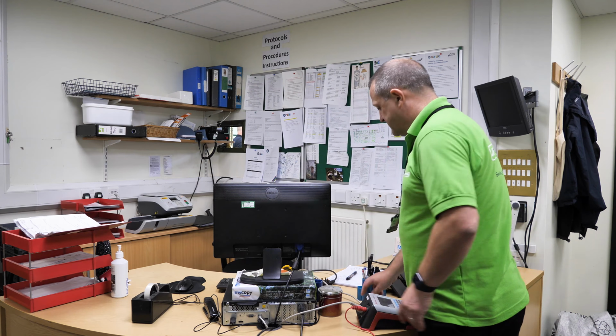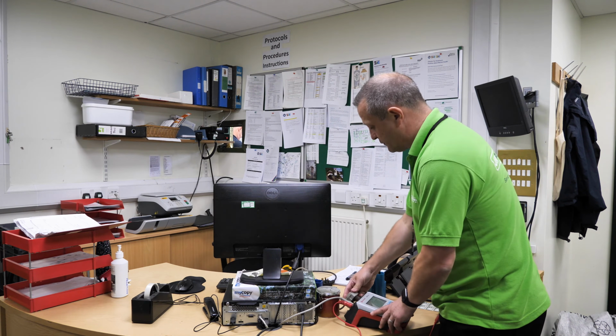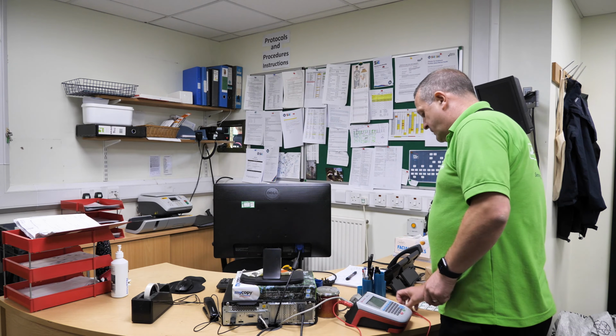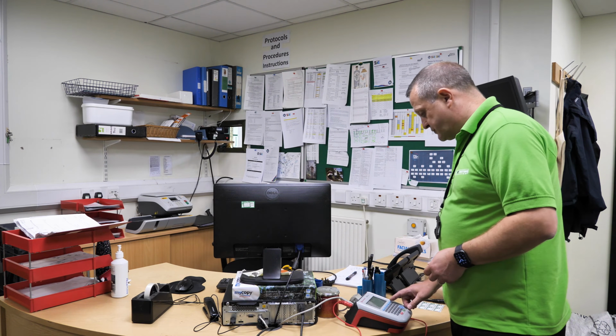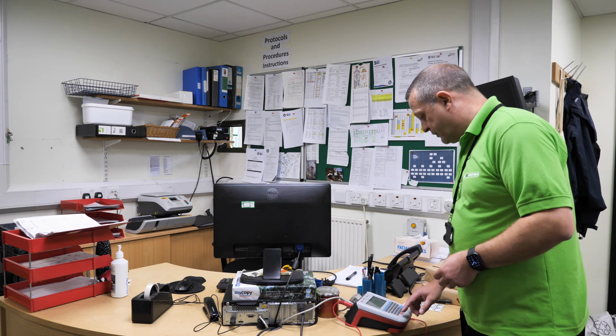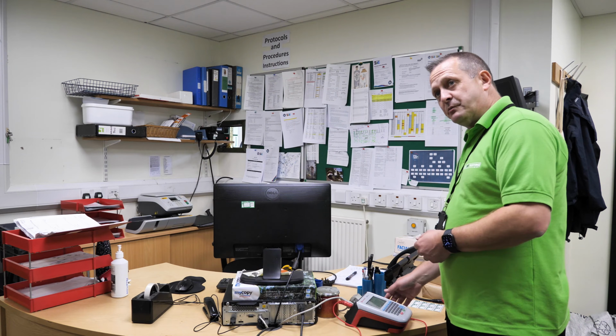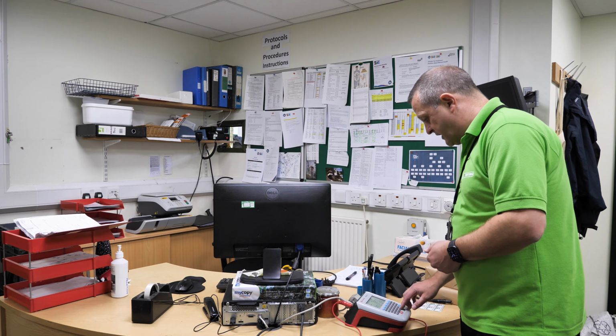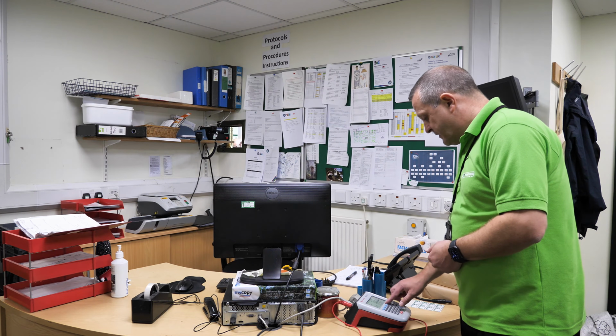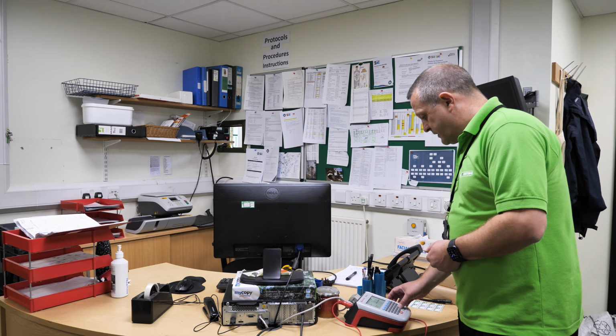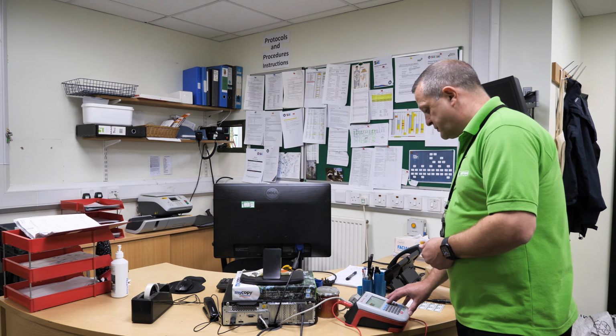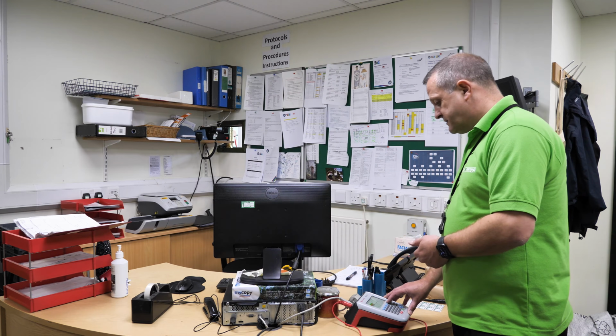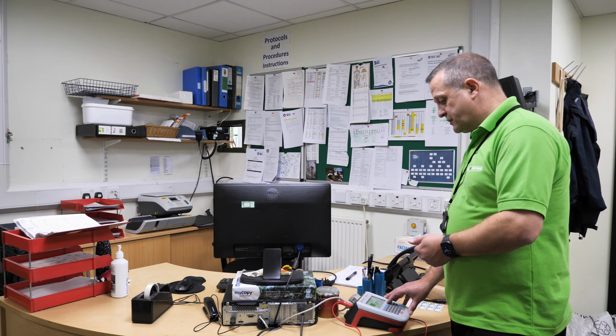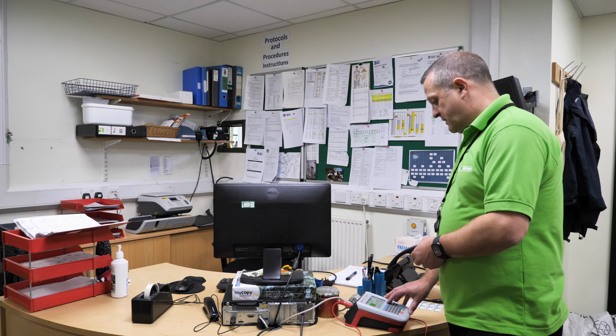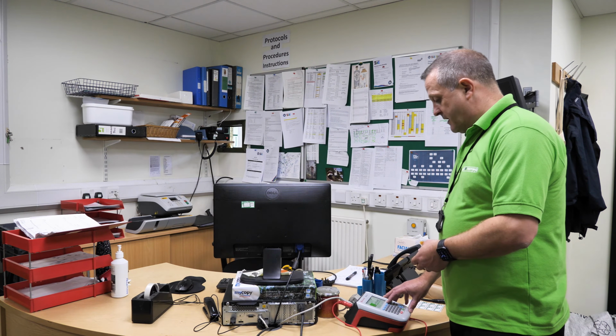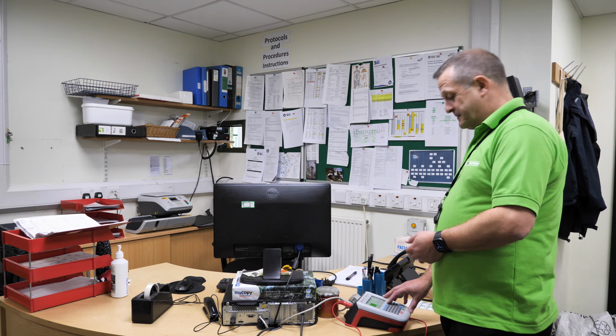So we're going to plug the IEC lead into the machine. Thankfully this cable is long enough to reach round. Put the plug into the PAT testing machine, and we're just going to conduct a Class 1 appliance test. My machine is actually pre-programmed to do IEC tests, so I'm just going to select the appropriate test on the machine, and then it's going to go through the process. So it's now going through the test, testing the IEC lead for its earth continuity, its insulation and its polarity. And thankfully on this occasion this lead is all good and safe to go.